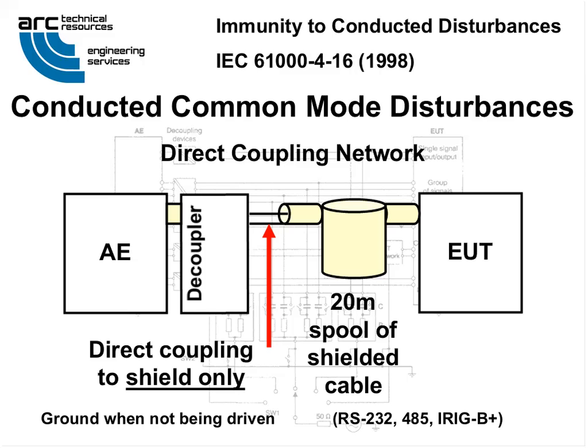Direct connection from the attenuator's output is applied to the shield conductor only, shown on the red arrow there. And you make sure to ground this point as you would normally when it's not being driven.